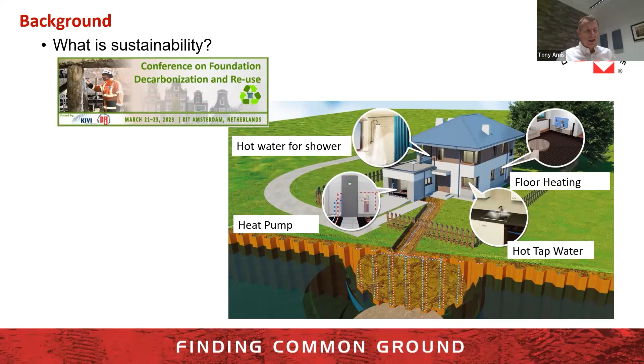Fundamentally, what we're looking at is a ground source heat pump. A lot of you probably have heard of air source heat pumps. The key difference is that with an air source heat pump, we're utilizing the air temperature at a moment in time to deliver heating or cooling. So when it gets very cold in wintertime, the heat pumps have to work extremely hard. Similarly, in summertime, when trying to provide cooling, the air source heat pump is exchanging heat with air that's already very warm.